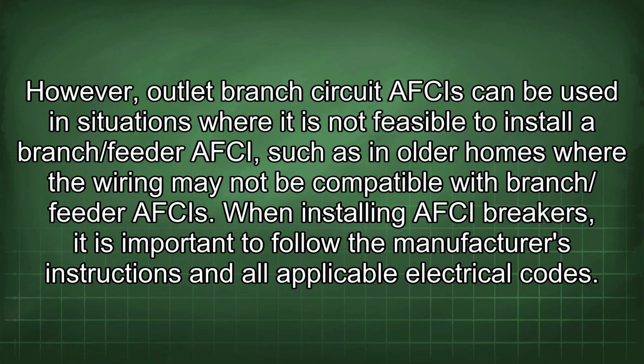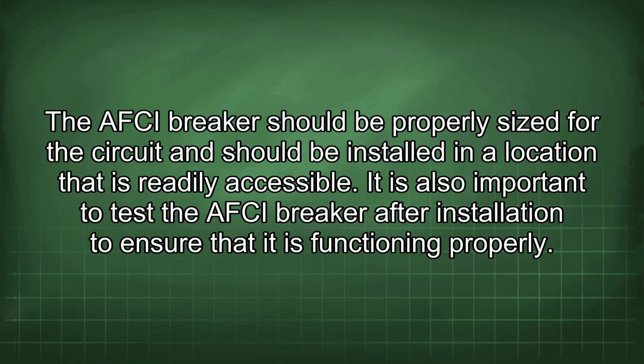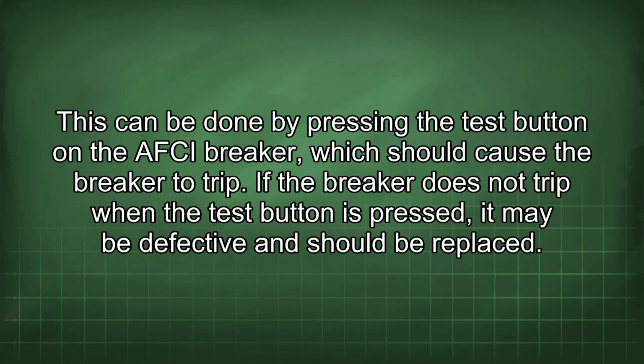When installing AFCI breakers, it is important to follow the manufacturer's instructions and all applicable electrical codes. The AFCI breaker should be properly sized for the circuit and should be installed in a location that is readily accessible. It is also important to test the AFCI breaker after installation to ensure that it is functioning properly. This can be done by pressing the test button on the AFCI breaker, which should cause the breaker to trip. If the breaker does not trip when the test button is pressed, it may be defective and should be replaced.